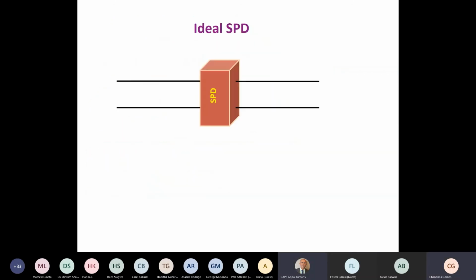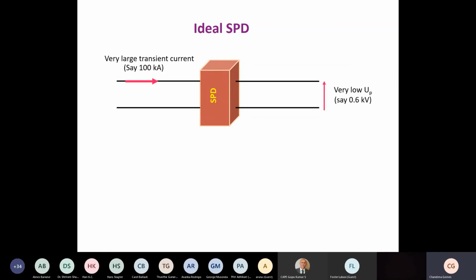Great. And then, if it is an ideal SPD, what we can expect is, ideal means something out of this world. It will be able to handle very large current, say that it can withstand 100 kiloamperes. And after withstanding 100 kiloamperes, it should give very low UP, like 0.6 kV. If we have such a SPD, it's wonderful.